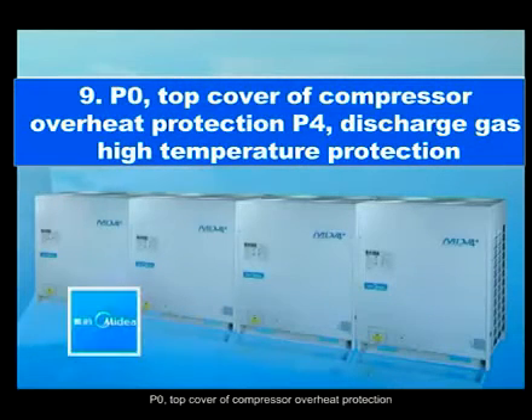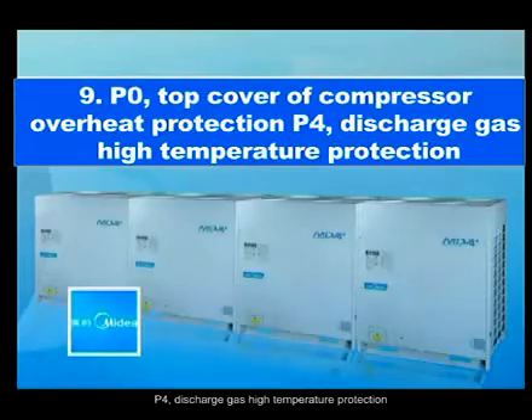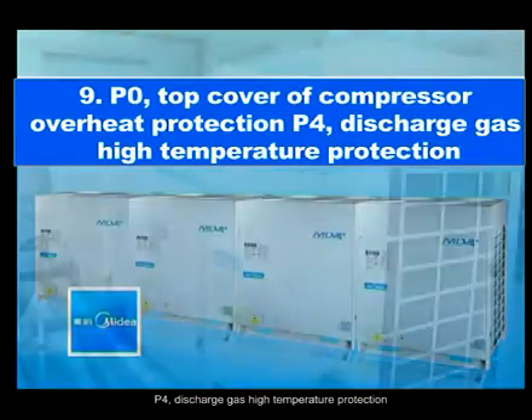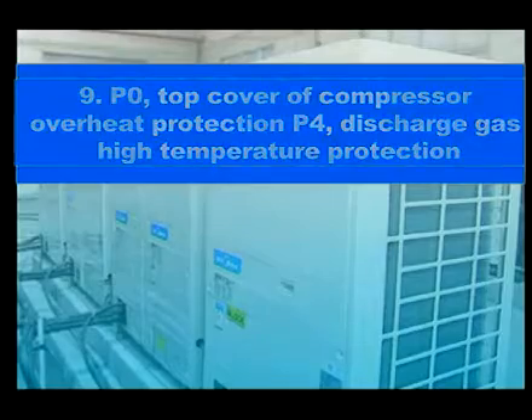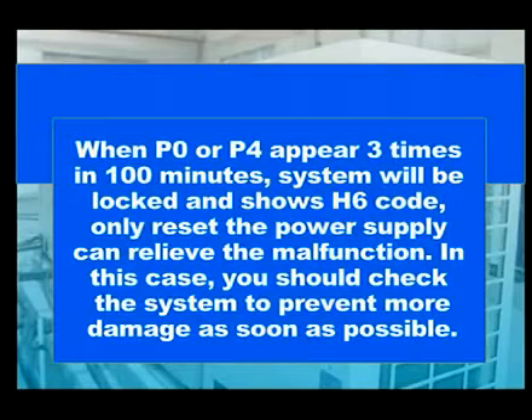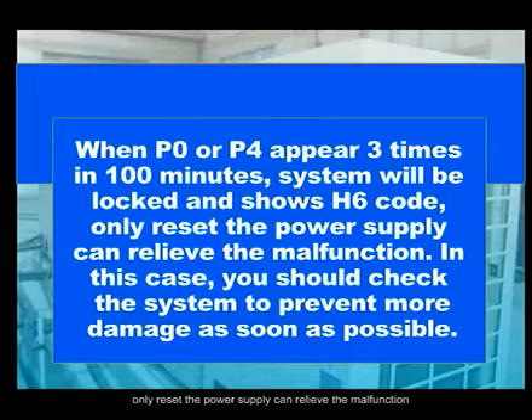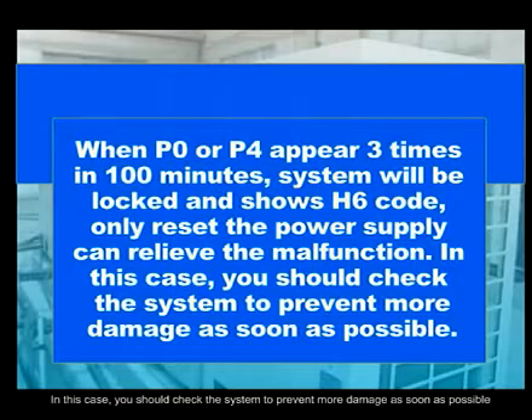P0. Top cover of compressor overheat protection. P4. Discharge gas high temperature protection. When P0 or P4 appears 3 times in 100 minutes, the system will be locked and show the H6 code. Only resetting the power supply can relieve the malfunction. In this case, you should check the system as soon as possible to prevent more damage.